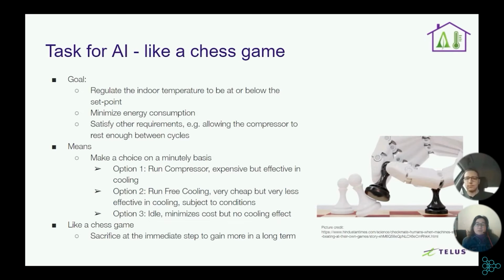Option 2 is to run free cooling, which you could think of analogously as opening the window and letting in the cold air. This is a much less expensive way of cooling, but it's also not as effective, and it's subject to conditions — for example, if it's very hot outside during lunchtime, you cannot necessarily use free cooling.